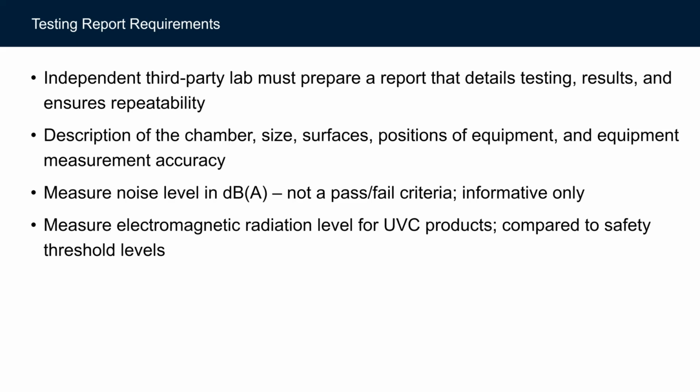There's also going to be a noise measurement. It's not a pass-fail requirement, but you want to know if you're putting something in the space, how noisy is it? And if you're using UVC, they have to measure the electromagnetic radiation level that UVC produces. And then you compare that to the safety threshold levels in 241.